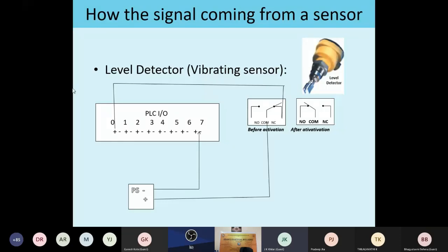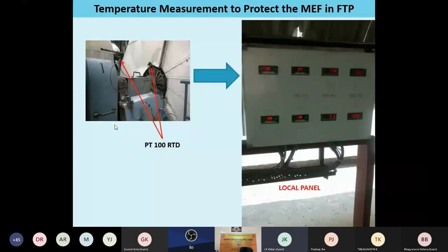Suppose now the PLC is getting a 24 volt power supply, and here all the negatives of the PLC cards are shorted and connected to the same power source. A different power source is not possible. With the same power source, the negative is connected to the PLC negative, and these negatives are shorted among themselves, and the plus will be connected to the NC point. If the level is not reached, the PLC is getting a plus signal, but when the level reaches this stem, the vibration will stop and the contactor position will change, and then the PLC will get 0 voltage. Similarly, we get the signal in the control room.